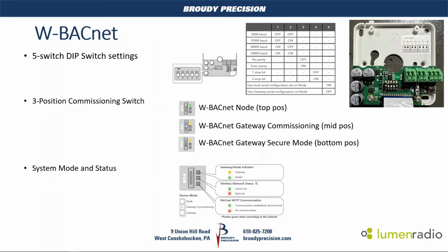The setup is quite simple, and looking at the diagram here, first here's a picture of the actual device. There's 24 volts in, there's another set of push-in terminals for power back out to go to another device, and then you have your BACnet MSTP terminations. There is a 5-switch dip switch package here, which allows you to set the baud rate, the parity, and the stop bits, and whether or not the node will set the baud rate or let the gateway do it. When I've been working with this device, I've been just setting the baud rate at each of these nodes. Basically this is the setup I go with: 1 on, 5 on, rest off.